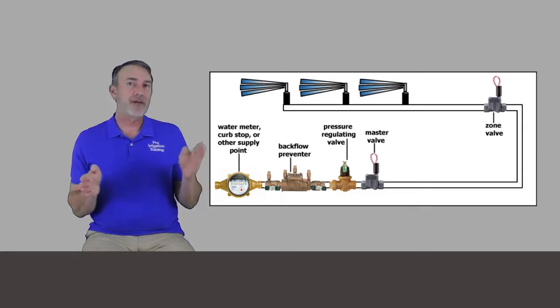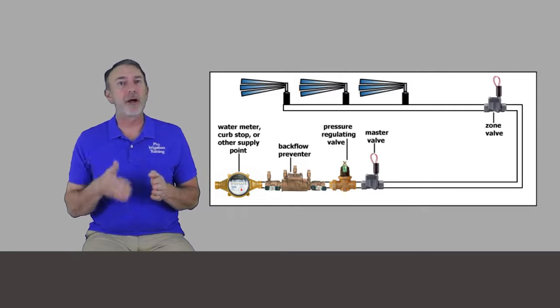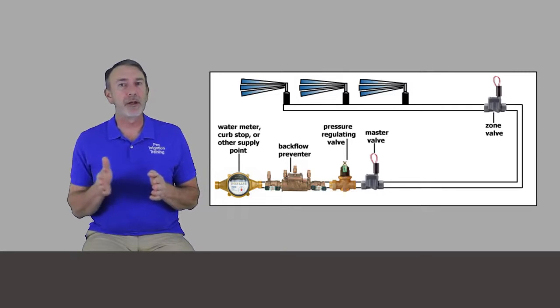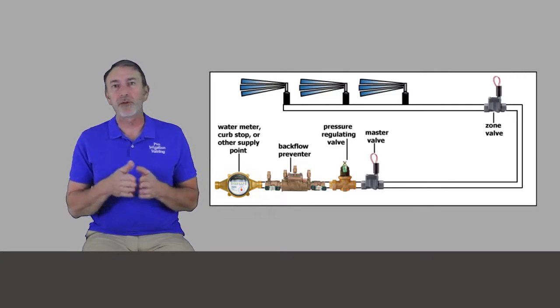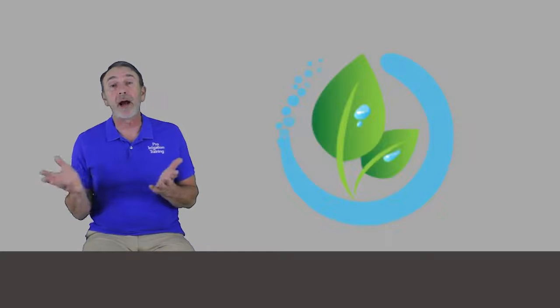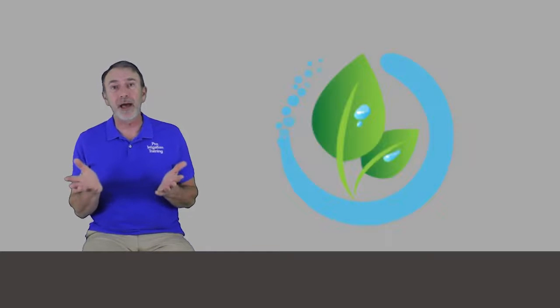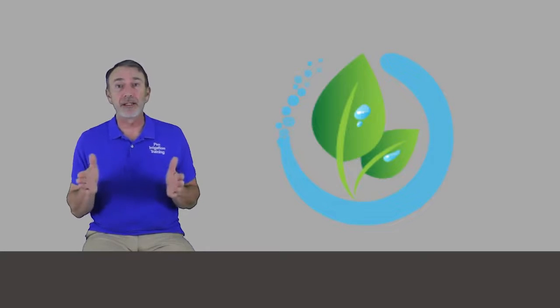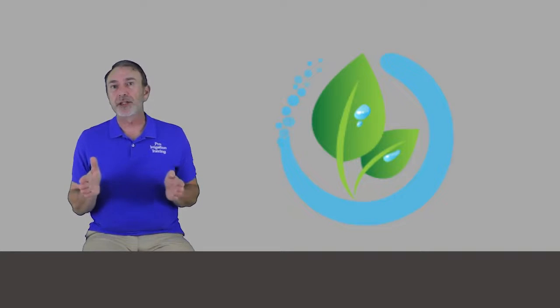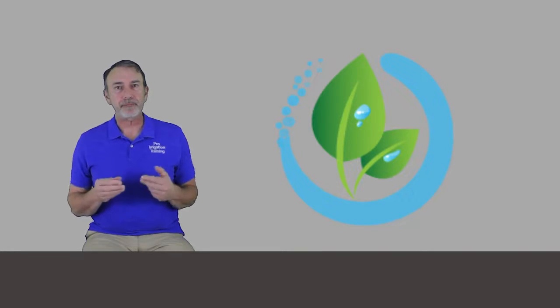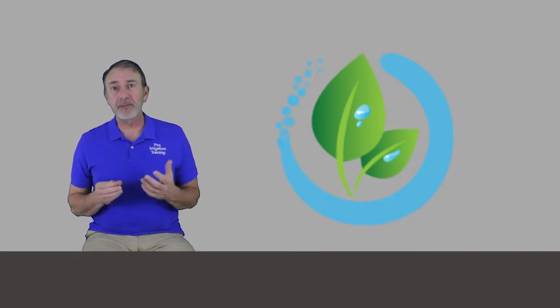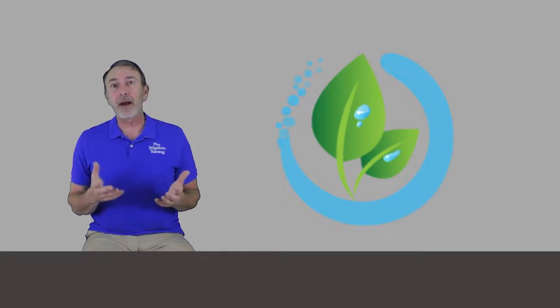What happens is when the timer turns on valve number one, not only does it turn on that zone valve number one, but it turns on the master valve as well. The master valve stays open while the timer runs through the cycle of zones, and then when the cycle is done, not only does it shut off the last valve, but it shuts down the master valve.